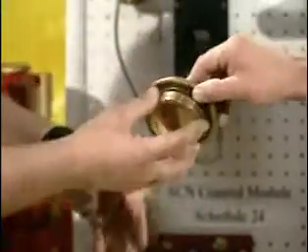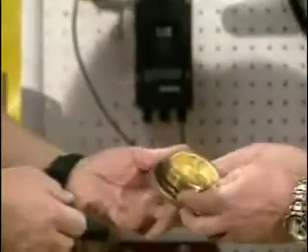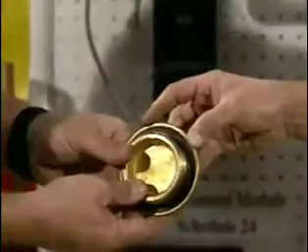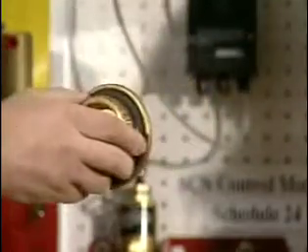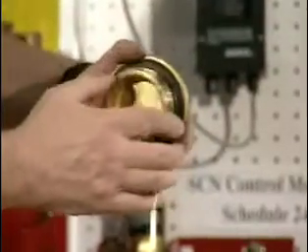And we talked about the O-ring and the gasket on the bottom. This is what you were talking about? Right. These need to be kept greased. On a semi-annual inspection, these caps should be pulled. The chemicals should be checked from the top as well as the bottom, and these rings should be greased.